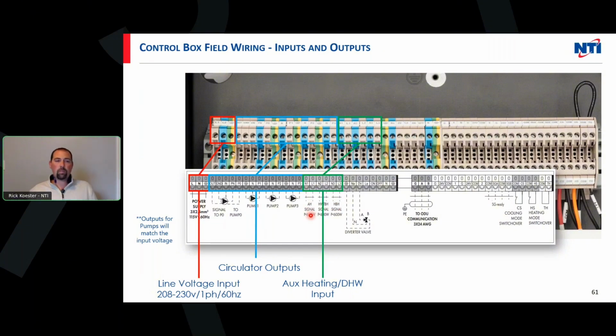So you've got some options here, depending on the contractor's applications and what he's doing. It gives us some room to play around with not just maybe a hybrid or a fossil fuel boiler, but also if there were electric elements inside the tank, we can utilize the elements as well as the backup boiler, and we can switch out priority, which we'll talk about a little bit too. So if I want one to come on before the other, we have that. We do have a diverter valve terminal here, and then we have our communication.